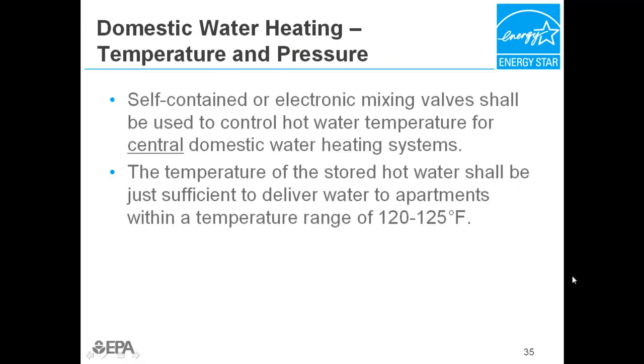Self-contained or electronic mixing valves shall still be used to control hot water temperature for central domestic water heating systems. Mechanical tempering valves are still not permitted. The temperature of the stored hot water shall be just sufficient to deliver water to apartments within a temperature range of 120 to 125 degrees Fahrenheit. This delivery temperature is verified during inspections.